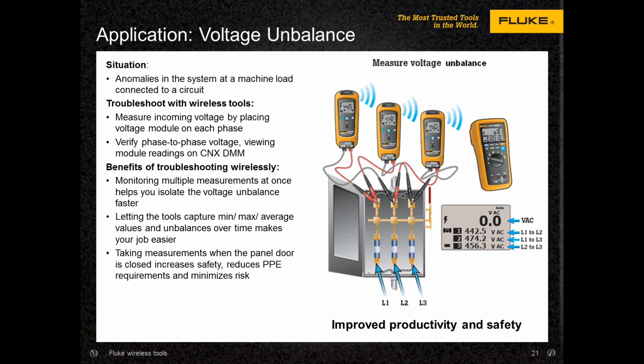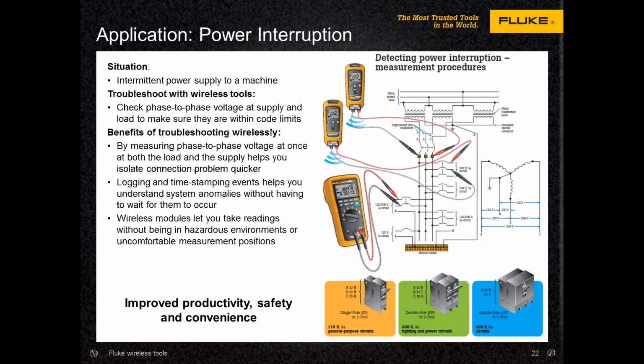Outdoors up to 600 volts, indoors up to 1,000, depending upon where you are in the distribution system. If you're talking about underground transformers, that's electrical power run over to an external facility. That's where the Cat 4 600 volt rating comes into play, especially for line power type measurements.